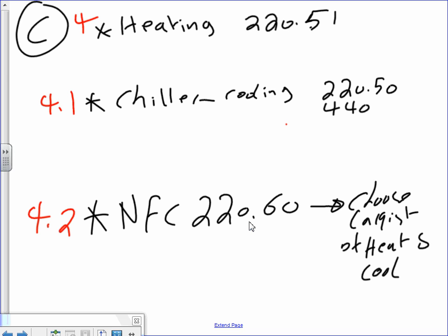For heating, John, please, when I say go there, please go there and just look at it, because you've never seen that. 220.51. If you guys go there, it will tell you, you're basically going to use nameplate value for all these heating equipment, right? 220.51, no derating, no value. So remember, I had three heaters.